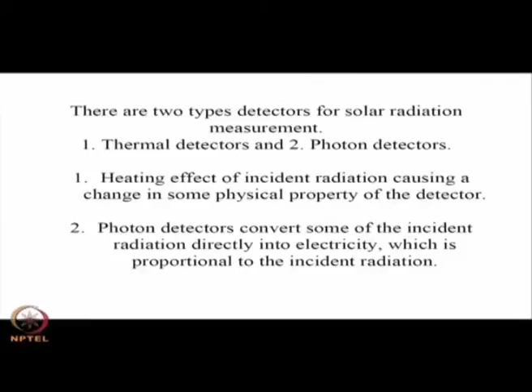Basically, the solar radiation measuring instruments make use of two types of detectors for solar radiation measurement. One type are the thermal detectors, and the other type are the photon detectors. The thermal detectors essentially produce a temperature differential between a heated part and a not so heated part, and the temperature difference is proportional to the solar radiation that comes onto the instrument. Whereas, the photon detectors directly convert the solar radiation to electricity. The amount of voltage generated is an indication of the incoming solar radiation.